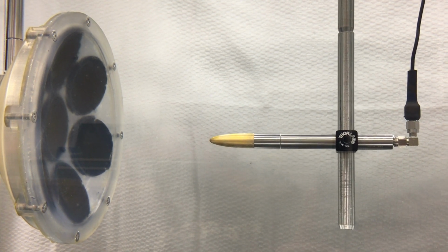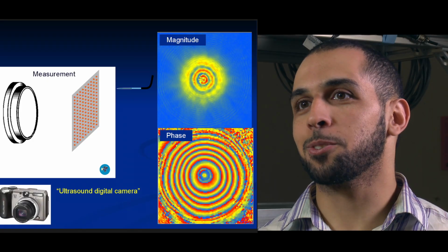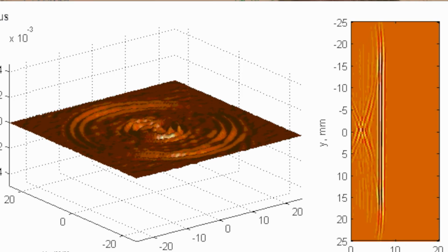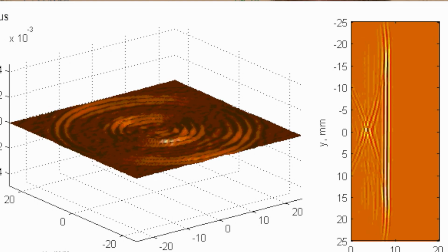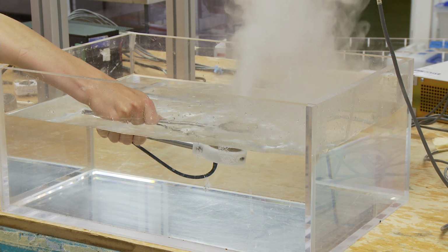The computer sends a signal to trigger the transducer, and the hydrophone collects the data points. Then the hydrophone moves, and it communicates to the computer to send another signal to the transducer, and the cycle continues. We capture all of the energy of the acoustic beam emanating from the source transducer, and then we can mathematically backpropagate the field and reconstruct what the field was on the surface of the transducer. For ultrasound waves, the equations that govern propagation in water or in the human body are well established.